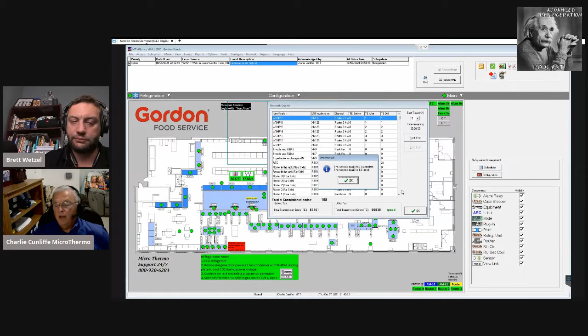It's plus or minus 5%, no more, no less. Now, this is an incredibly tight network, one of the best that I've seen. Remember, 11 to 20 is very good and 1 to 10 is excellent. This is 1.3, so that means the actual physical wiring itself, all of the connections, all of the errors since this store has been running. This is one of the best stores I've seen, 1.3, as close to zero as I've ever seen. This is a very, very tight network, so you'd expect no loss of any nodes, no loss of information, nodes not dropping off and disappearing.